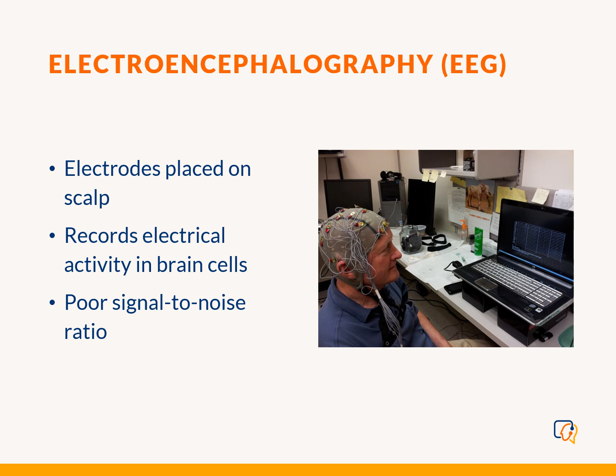There are a couple of different types of EEG electrodes. These are wet electrodes. The ones on the right are sort of cup-shaped with a little opening that would be filled with a conductive gel. Not all of them are cup-shaped, but most of them do have a hole in it where you would use a blunt-tip syringe, like you see in the photo, to insert a little bit of conductive gel. That fills in the gaps between the electrode and the scalp. Typically there's some hair or some other space there.